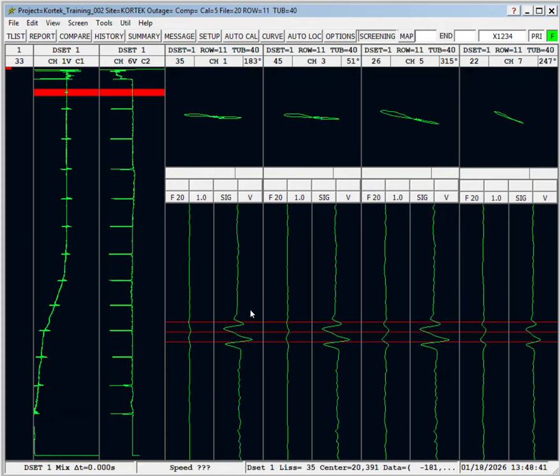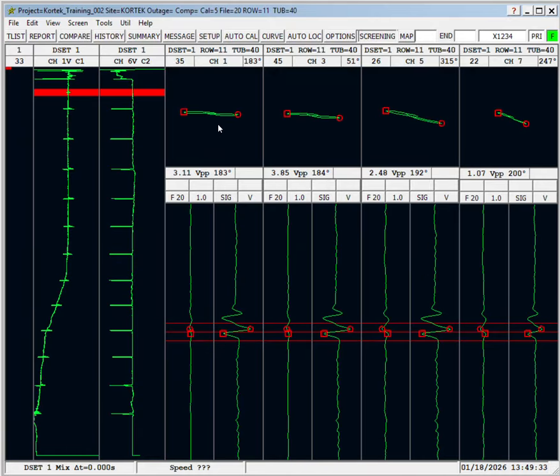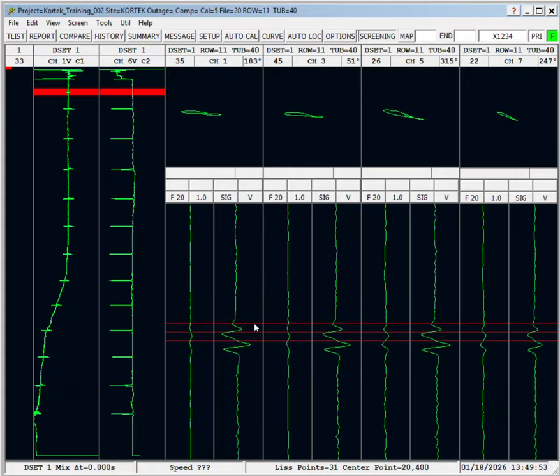Let's go to the next dent right next to it. That one looks pretty much the same. It lies pretty flat on all the differential channels. I would just report that as a dent. Now normally I'd have a button set up in here called a flag key, where you could just click it and it would make this entry to your report. This is a dent signal, and I would also report that as a dent signal. Now your ETSS sheets, they'll contain all of the 3-letter codes that you can use during your inspection. One of the things listed on your ETSS would be a dent. You'd enter that as a 3-letter code, DNT.